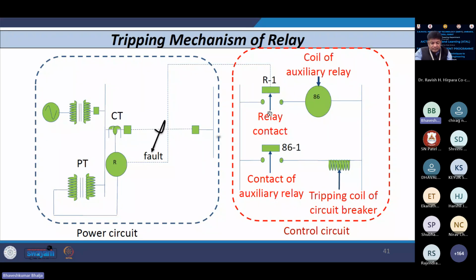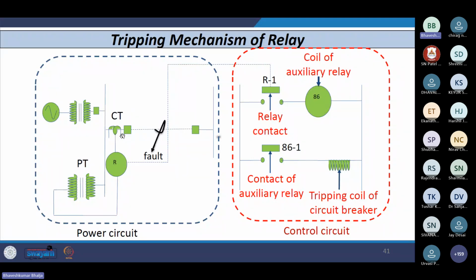The contact closes depending upon the severity, the magnitude of the fault. Usually it is time delayed in nature, right? An inverse time characteristic is there. So this coil is energized and its contact closes, and then the trip coil of the circuit breaker is energized and this becomes open. Now, after this point, when the breaker becomes open, the task of auto reclosing starts. So the auto reclosing mechanism will wait for some time, right?